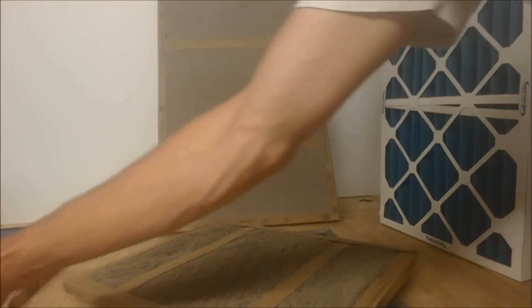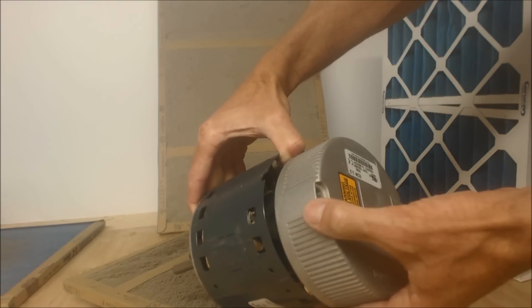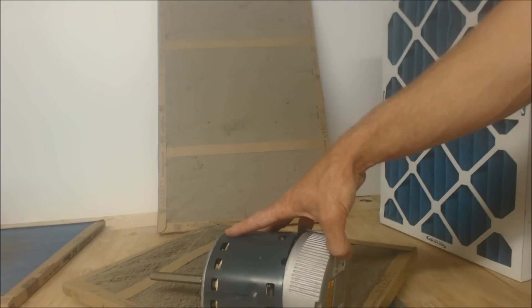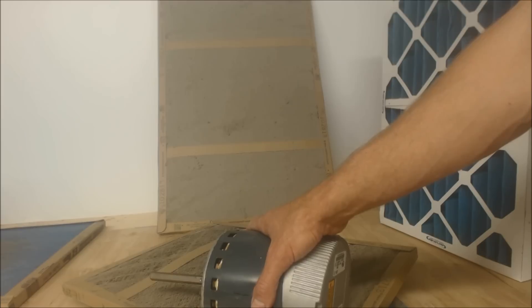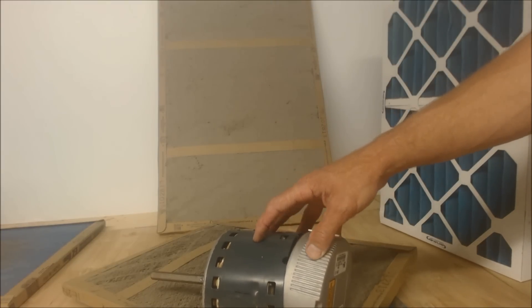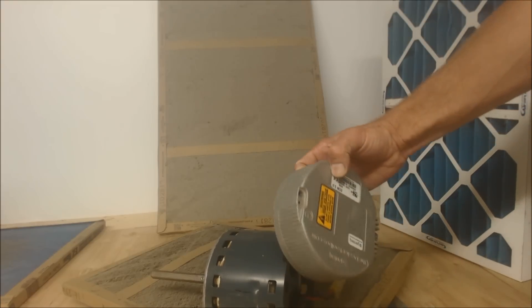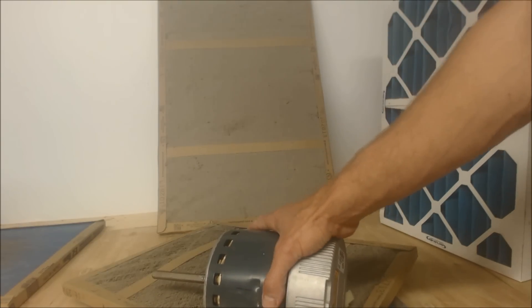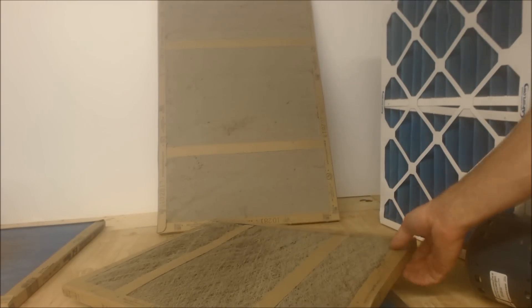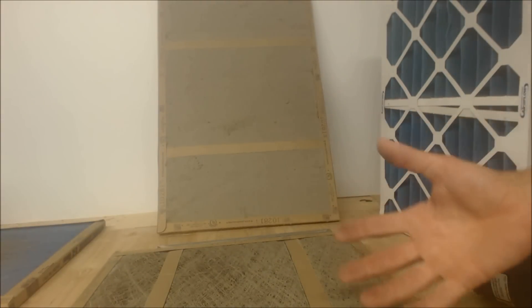In the case of a variable speed blower motor — like this ECM 3.0 — it's going to work harder to overcome the friction from a dirty filter, which costs more electricity. It will try to overcome the resistance until it draws so much amperage that it ends up breaking. I've had to pull variable speed blower motors out and replace the module multiple times due to very high resistance caused by a clogged air filter.